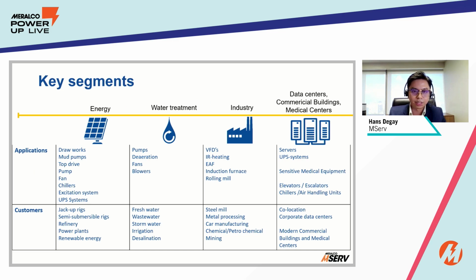Here are some key segments. Harmonics are generated by nonlinear loads. And if we look into your facility, you would know that mostly electronic components are the source of the harmonics, since they have switching actuation on their components. Some key segments are energy, water treatment, industry such as manufacturing, data center, commercial buildings, and even medical facilities. So anything with harmonics that are quite sensitive can need harmonic filters.